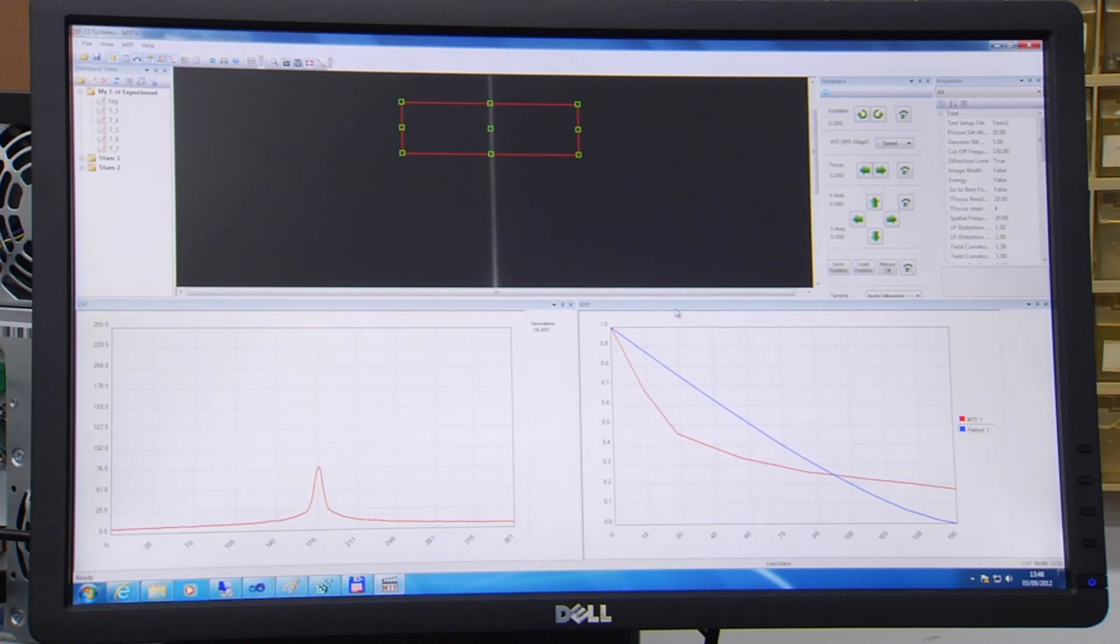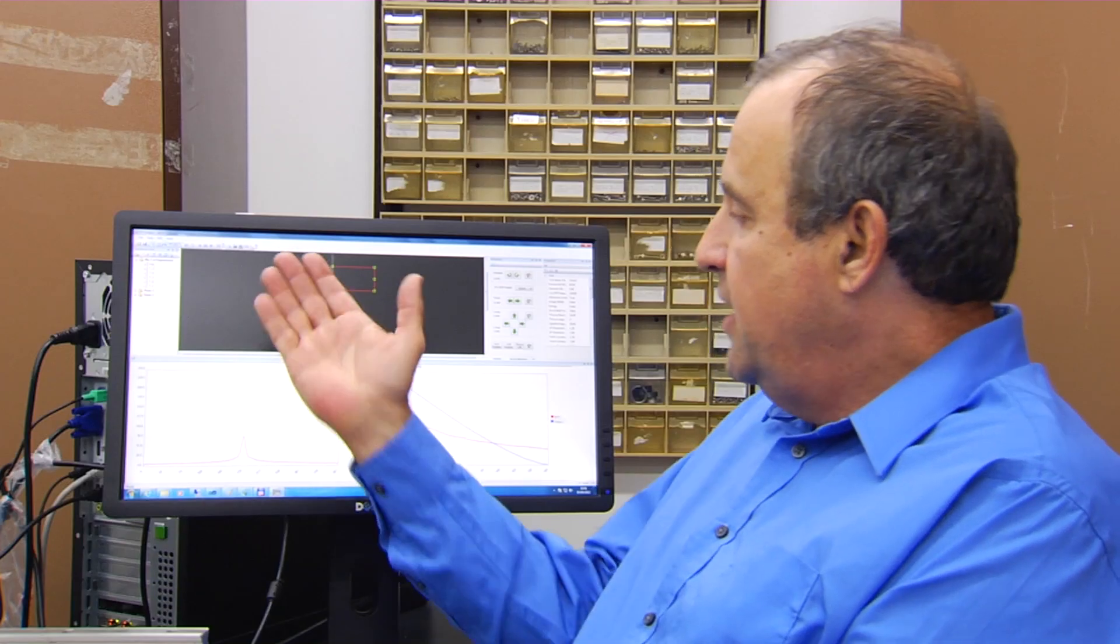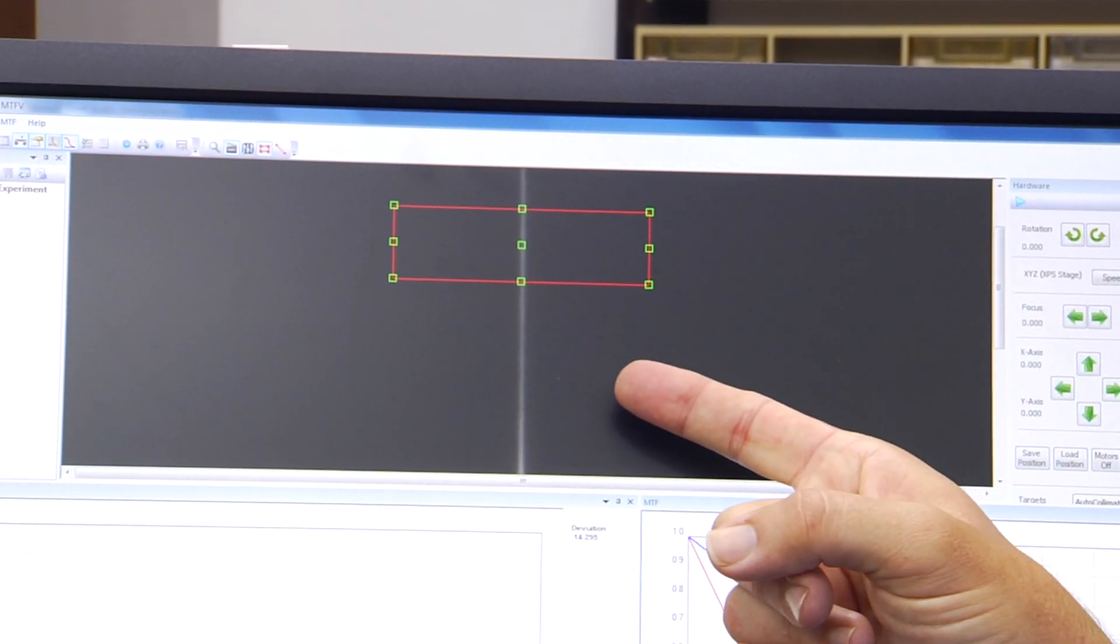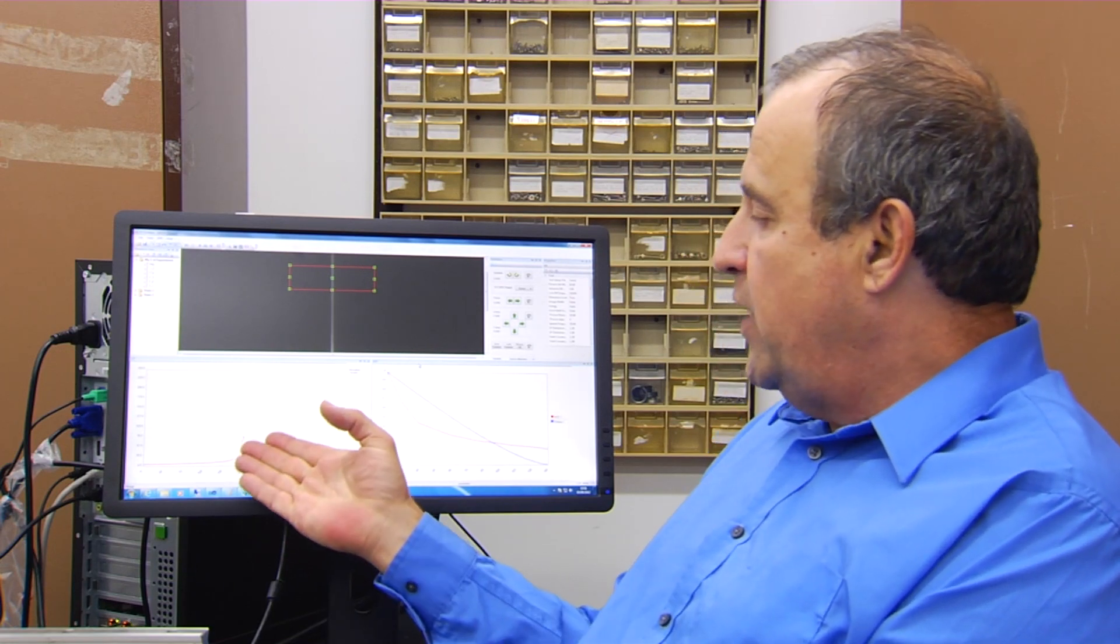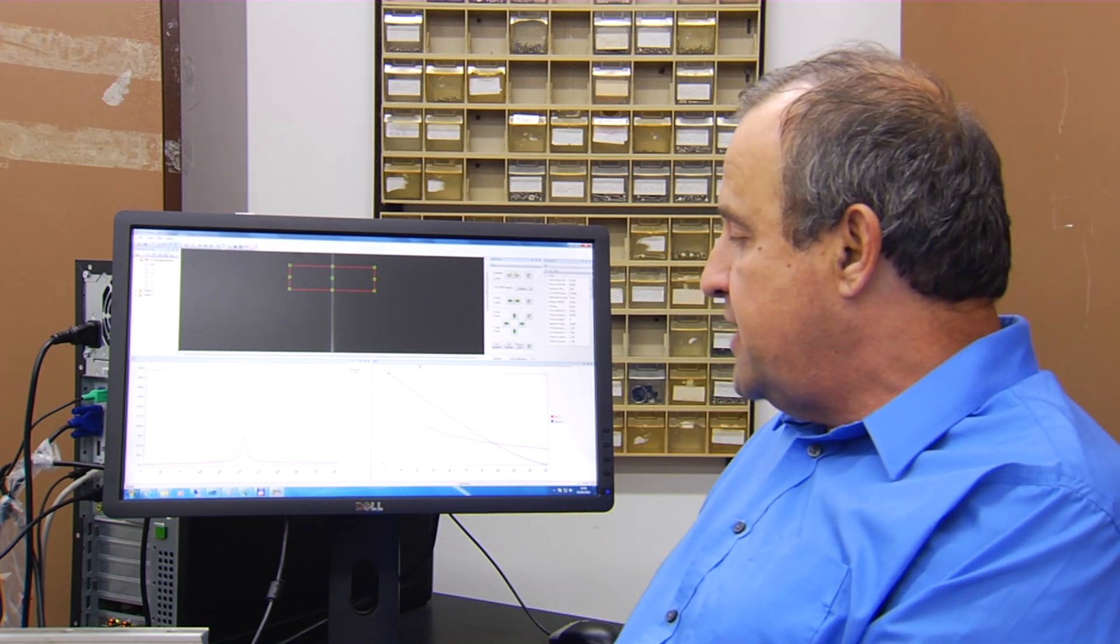For example, we have here a screen performing an MTF test. At the first stage we are choosing the region of interest on a slit or a step for performing MTF test. Afterward, we are obtaining the line spread function from which we are performing the Fourier transform and we are getting the final result of the MTF of the unit under test.